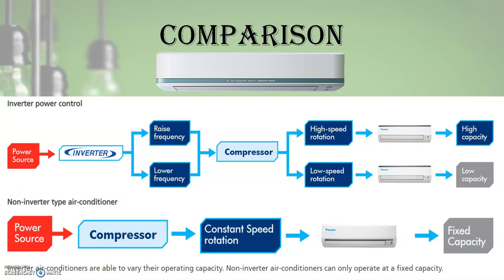Now let us see the comparison. The inverter power control and non-inverter power control are shown here. In the non-inverter type, the compressor motor always runs at a fixed speed and fixed capacity, and temperature is adjusted by turning the compressor motor on and off. In an inverter power control, there is an added inverter which can vary or control the frequency and thereby control the motor speed.